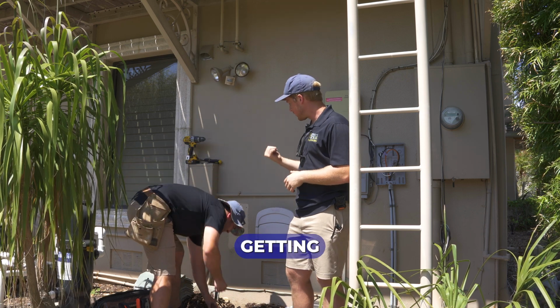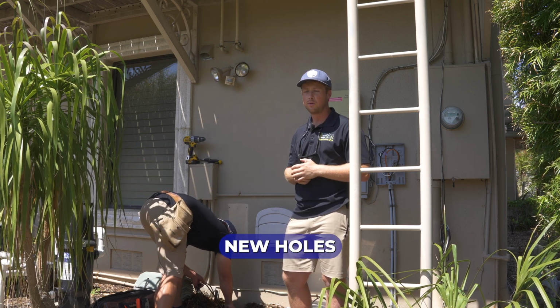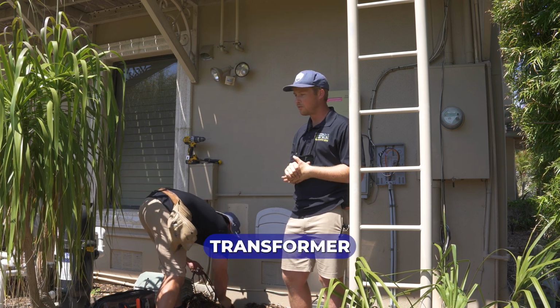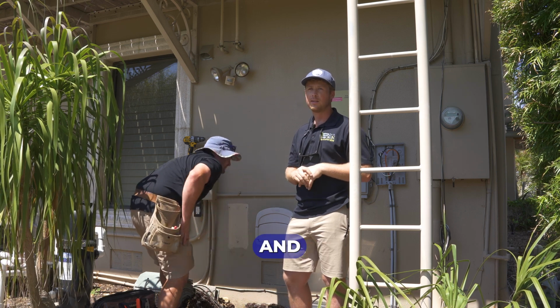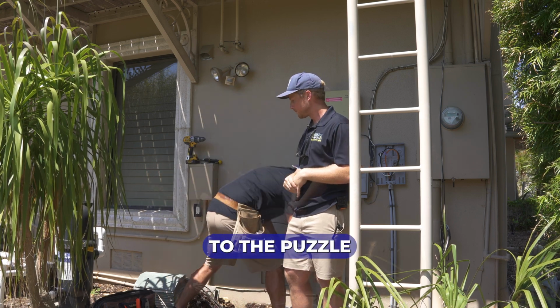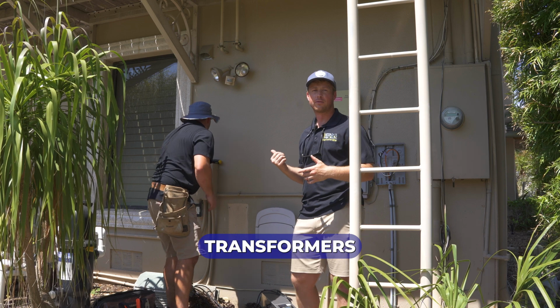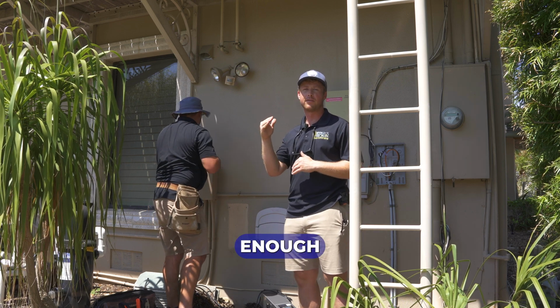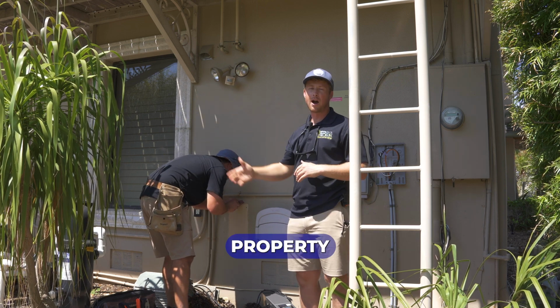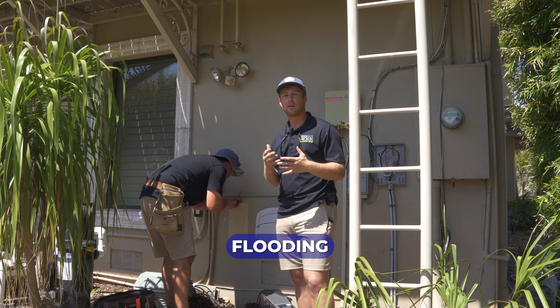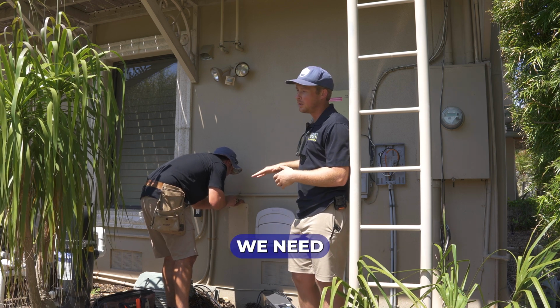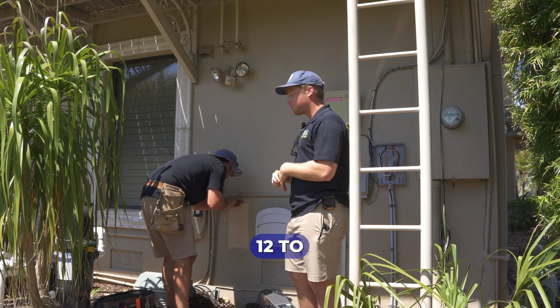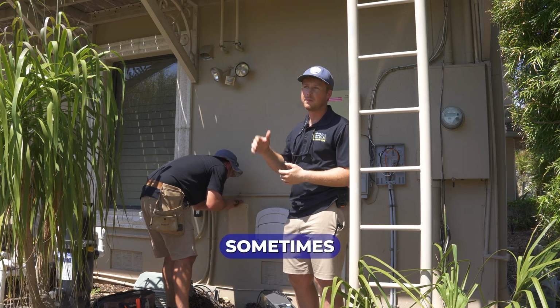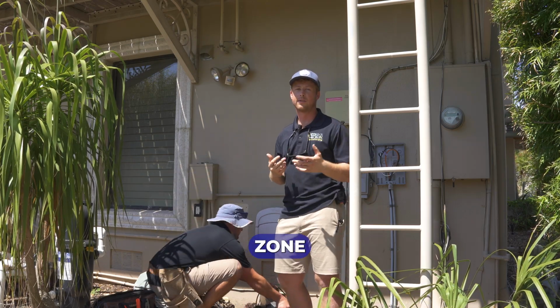And Zach's getting the holes prepped. We gotta drill some new holes, and then we will mount the new transformer, show you how we do that, and some other pieces to the puzzle. We gotta make sure that these transformers are mounted high enough, and the reason is, this property's on the water, so if there's any flooding or any sort of issues, we need to mount this transformer at least 12 to 24 inches typically, sometimes even higher if it's in a really risky flood zone.